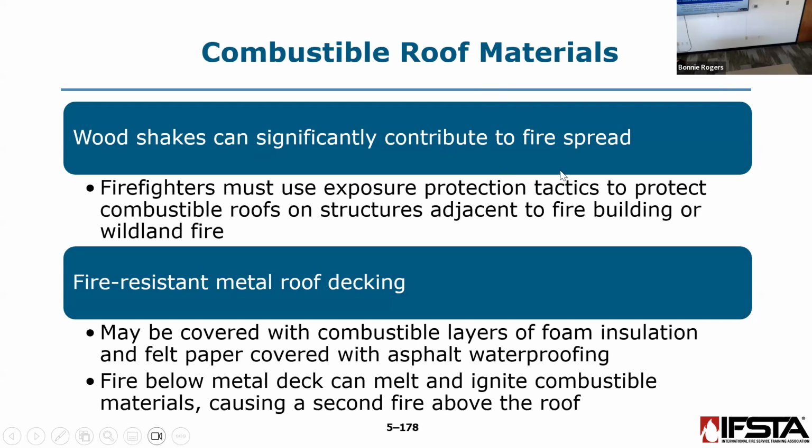Okay, so when we talk about exposure protection, what are some ways that we can provide exposure protection? Master stream. Okay, so we're gonna put water on it. And where are you gonna put the water? On the other. So building A is on fire, you're gonna be pouring water on the side of building B. Sure. Yeah, that would be a good tactic. We put a water curtain there. Oh wait, what's another way? Think outside the box.